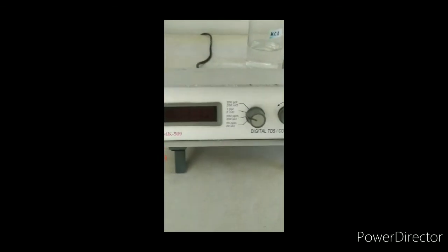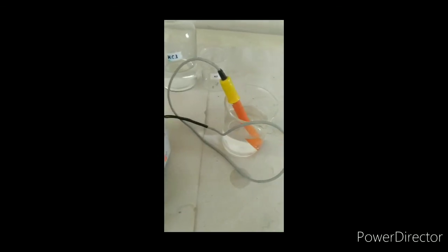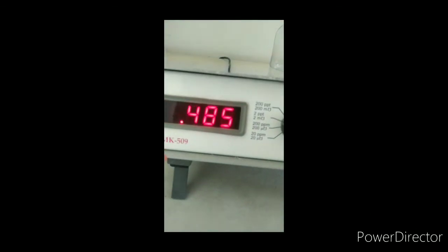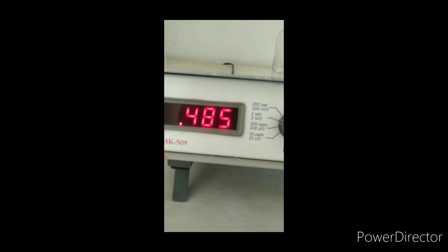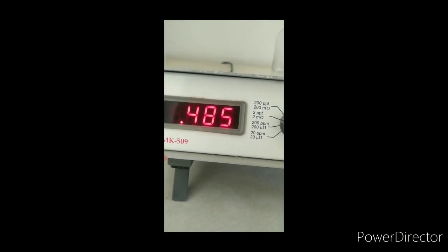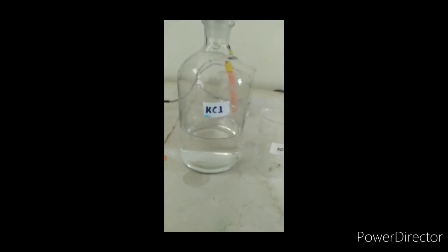I have already connected it. Now once again I'll switch the instrument on. Now it will show some conductance value of water. Any electrode for that matter, we must dip it in water and keep it there.